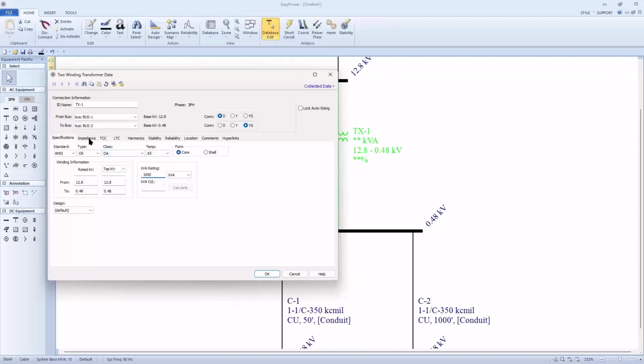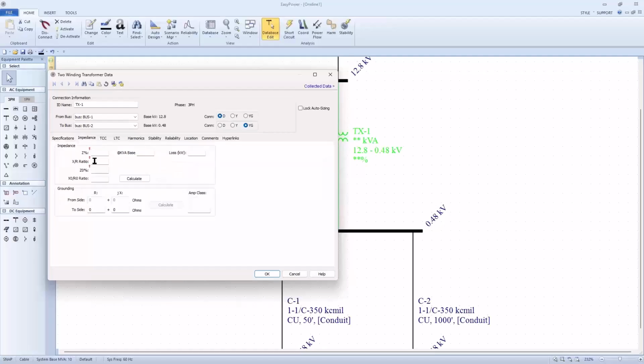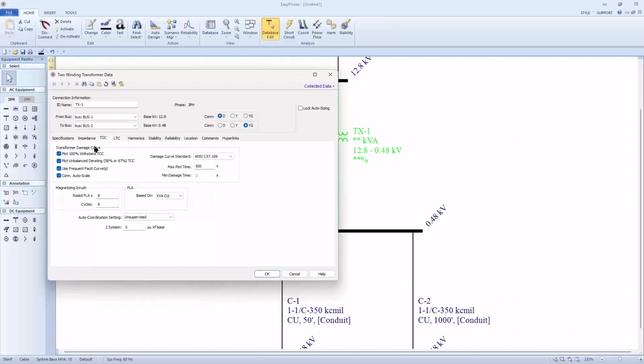We go to the impedance tab. I have more red dots. He said his Z impedance ratio was 5.75%. Now, the nameplate may not have the X over R or the zero sequence ratio, but the tool will calculate those based upon industry standards. And when we go to the TCC plots, it's going to plot my damage curves automatically using those parameters.